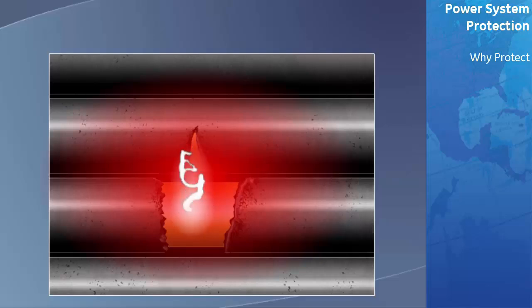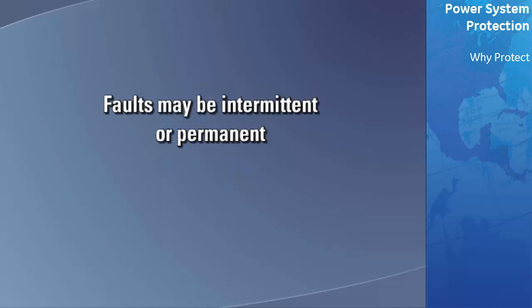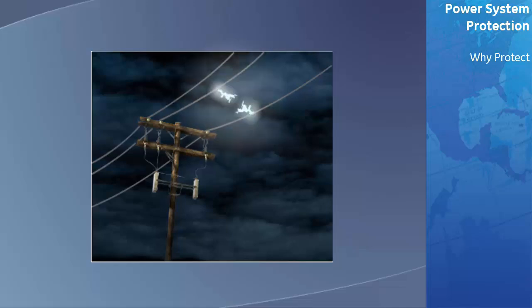There are many causes of power system faults — lightning, wind, and ice and snow, just to mention a few. The protective system must be able to sense the fault and take appropriate action within a time frame necessary to minimize damage. Faults may be intermittent or permanent in nature. Lightning striking the transmission line or a strong wind causing two phases of the transmission line to touch and form an arc are common causes of an intermittent fault to an overhead transmission line.